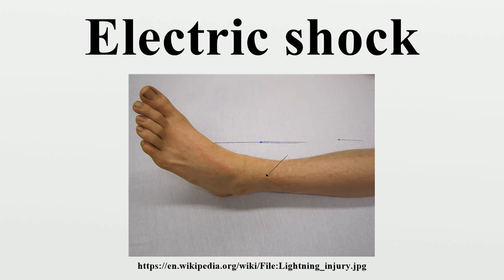Shocks can be caused by direct or indirect contact. Contact with an exposed conductive part under fault conditions is called indirect contact. IEC requires certain degrees of ingress protection against direct contact. Indirect contact protections can be achieved by earth equipotential bonding and automatic disconnection of supply, using fuses for example.